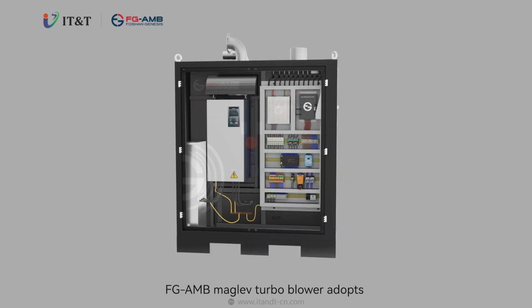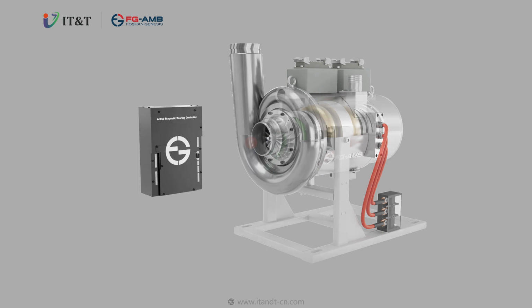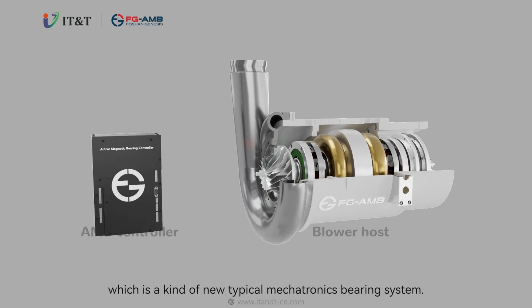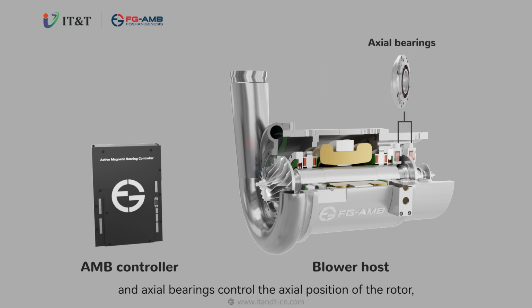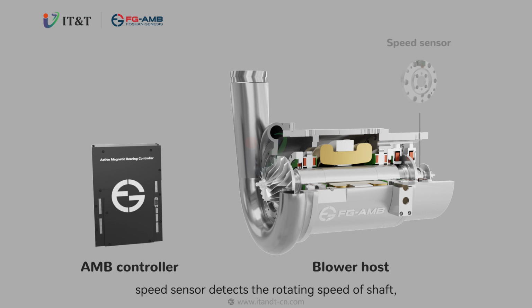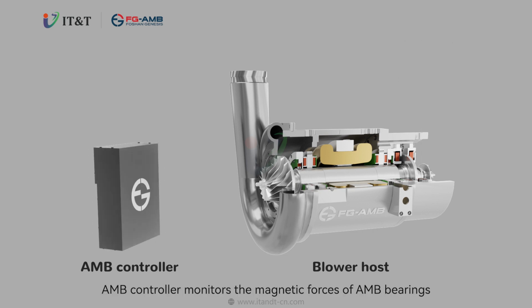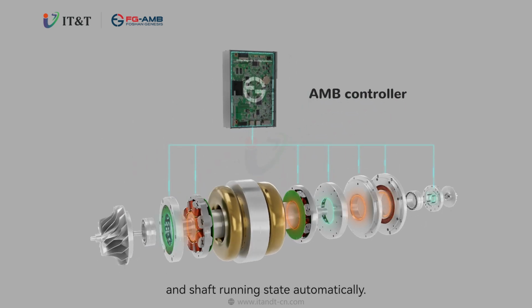FGAMB Maglev turbo blower adopts the most advanced active magnetic bearing and AMB controller, which is a new kind of typical mechatronics bearing system. Radial bearings control the radial position of the rotor, and axial bearings control the axial position of the rotor. Position sensors detect the rotor offset in the XYZ direction in real time. A speed sensor detects the rotating speed of the shaft. The AMB controller monitors the magnetic forces of the AMB bearings and the shaft running state automatically.